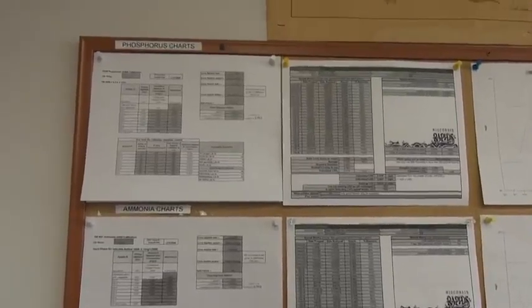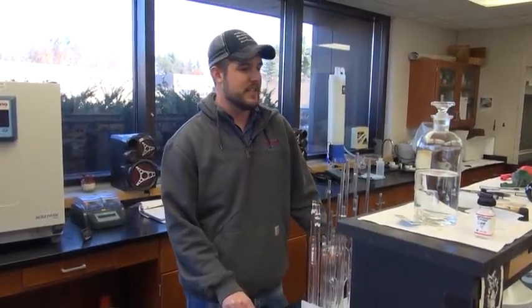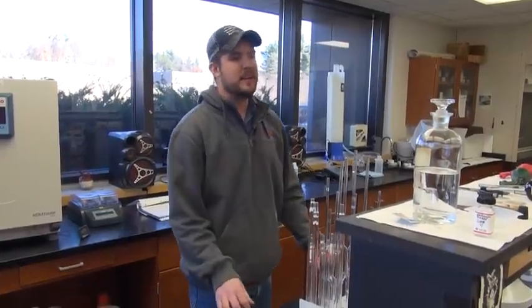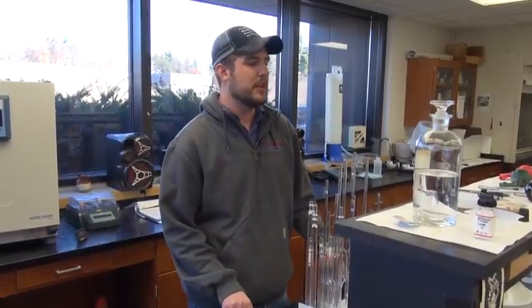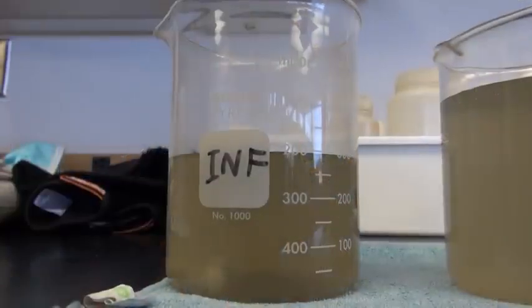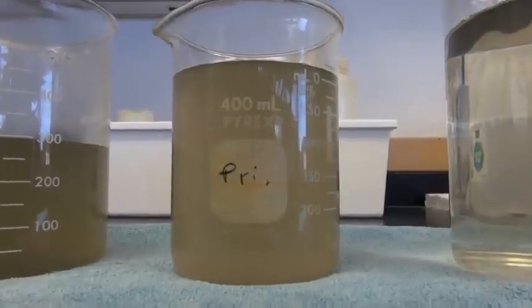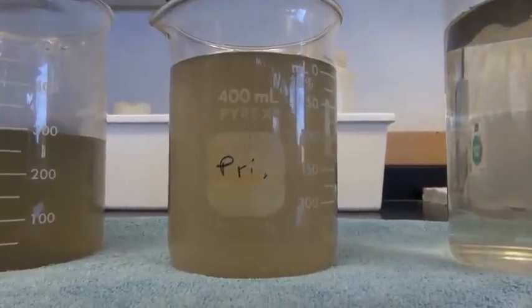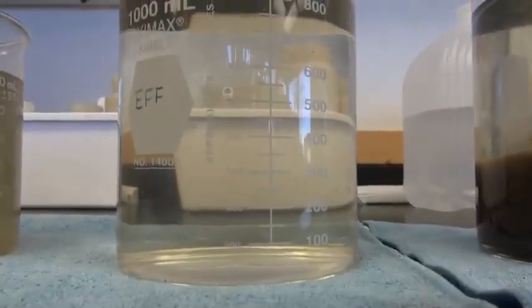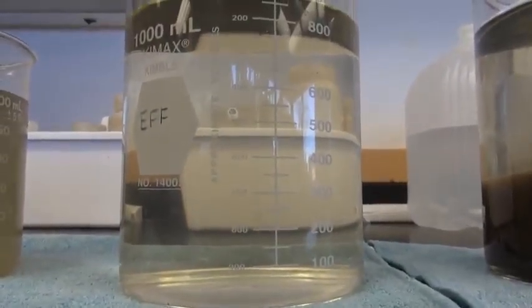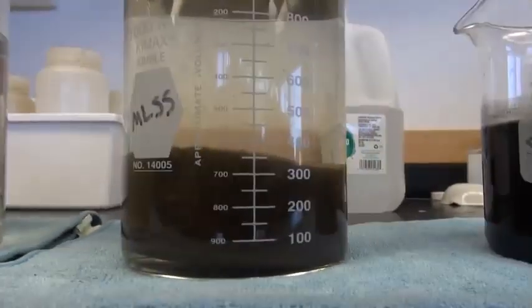One of the main tests we do is a total phosphorus test. We have to run phosphorus five days a week. We do it all in one batch because we're able to save samples. It's a more extensive test. Our permit on that is 1 milligram per liter, though we usually try to keep it around 0.5. That's a test that involves an acid digestion, and we read them out on a spectrophotometer.